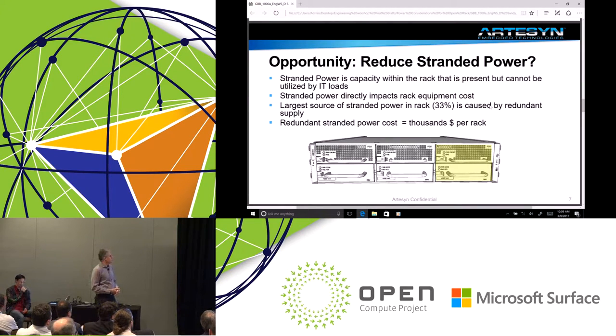So one of the questions we have is, are there ways to reduce stranded power within the rack? For those who don't know that term, stranded power is power where the capacity is there in the rack, but you can't count on it for use by your IT equipment because it's there for purposes like redundancy, or you've over-provisioned the supply just in case you hit a power peak. In this particular example, you see three PSUs across the top, three BBUs along the bottom. One-third of that is there for redundancy, so you've got about 33% stranded power in that rack. By reducing stranded power, you can dramatically reduce the cost of your power infrastructure. So that's the first question.